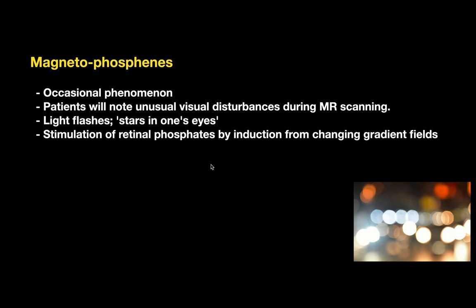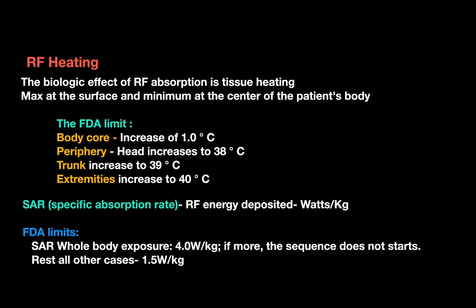Regarding radiofrequency heating, the biological effect of RF absorption is tissue heating — maximum at the surface and minimum at the center of the body. FDA limits are: body core temperature increase up to 1°C, periphery up to 38°C, trunk up to 39°C, and extremities up to 40°C.